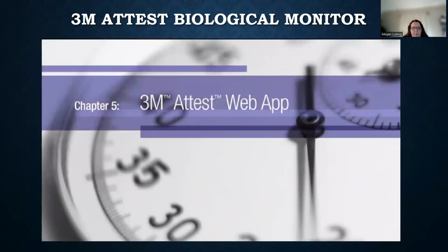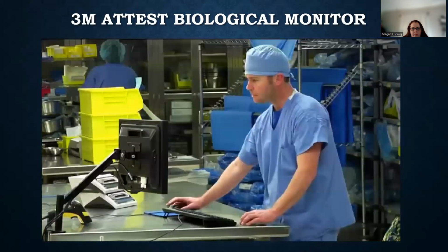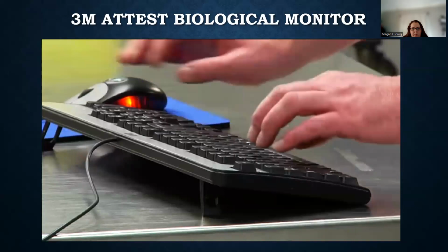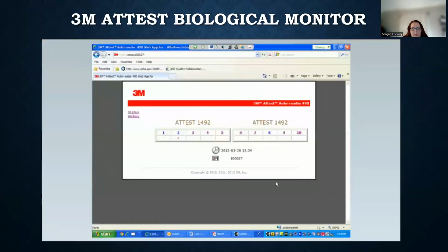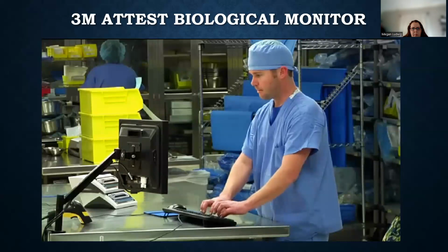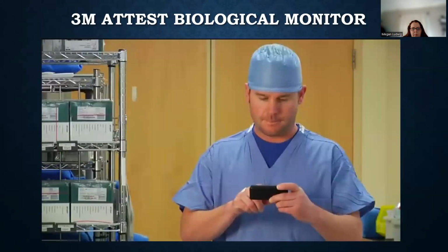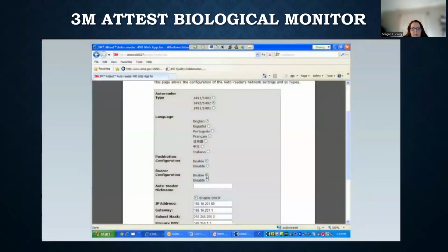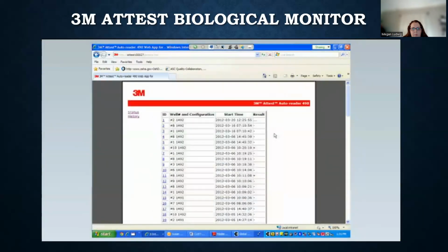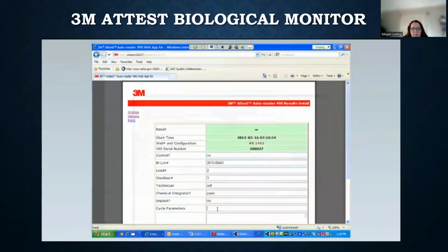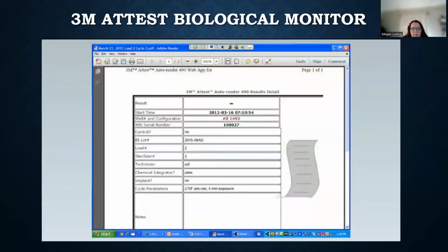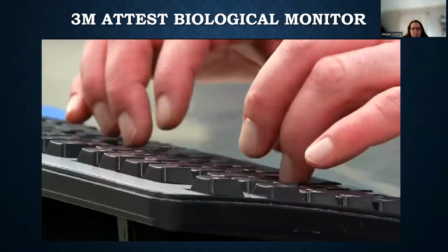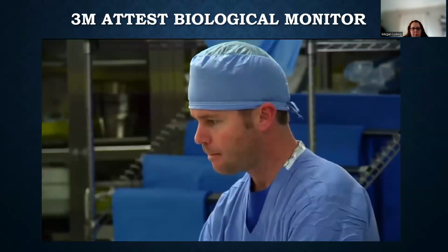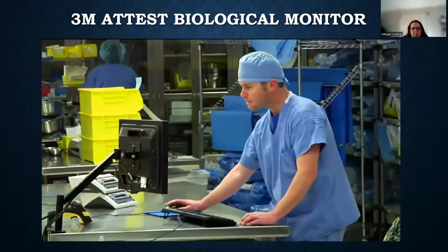The 3M Attest Autoreader 490 offers additional functionality online. Once you connect to the Attest web app, you can remotely view the current status of incubating BIs using a computer or smartphone. The web app also allows you to remotely view and configure Attest Autoreader 490 settings, view results for the last 100 BI tests, save records for your electronic files, and print records for your paper files. To connect to the Attest web app, follow the step-by-step instructions in the Attest Autoreader 490 Operator's Manual.